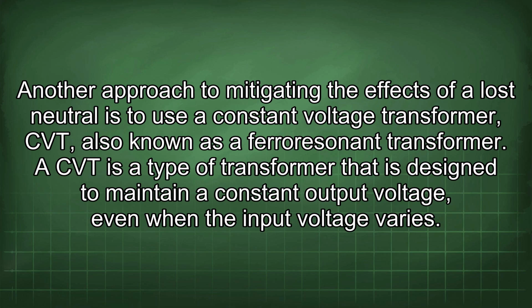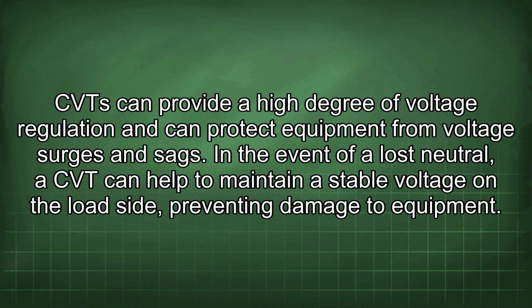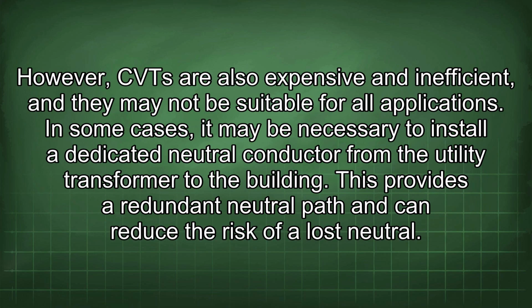If the neutral is lost on the primary side of the transformer, the secondary side will still maintain a relatively stable voltage. However, it's important to note that an isolation transformer does not completely eliminate the risk of damage from a lost neutral. Another approach to mitigating the effects of a lost neutral is to use a constant voltage transformer, CVT, also known as a ferroresonant transformer. A CVT is a type of transformer that is designed to maintain a constant output voltage even when the input voltage varies.